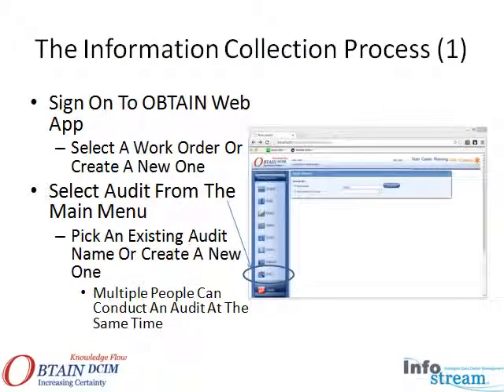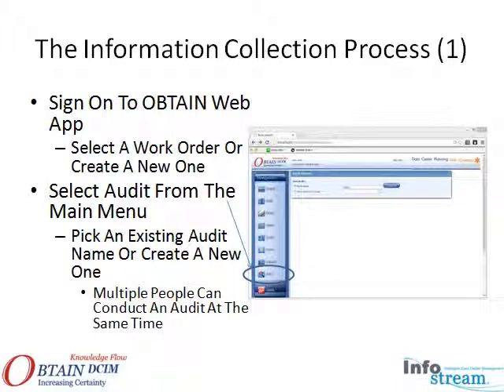Audits are easy and fast with Obtain. The information collection process produces an exception list of assets not represented correctly in the DCIM knowledge base. The collection process begins by signing on to Obtain with a mobile device on the computer room floor. When the user is signed on to an existing or new work order, they can select Audit from the main menu, then select an existing ongoing audit or create a new one. Multiple users can conduct the same audit at the same time, as the Obtain server can coordinate multiple inputs simultaneously.